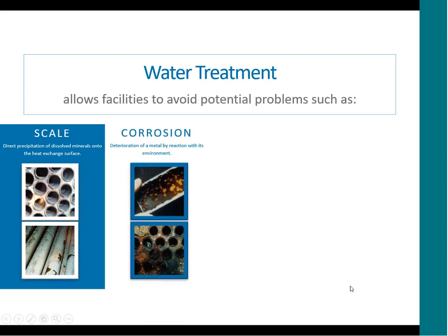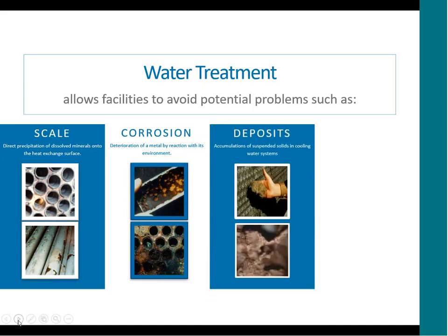And then we'll have corrosion. Corrosion can happen in the water systems since they're mostly made of metal. We have water, so corrosion can be a real problem. Corrosion is a real problem because once the metal's lost, it's gone. It has to be replaced. With scale, if you get scale formed on your systems, you can do an acid cleaning. You can get the scale cleaned up, and we can be back in business. But with corrosion, if you lose the integrity of your metal, you have to replace it. So that's not something that we want to happen.